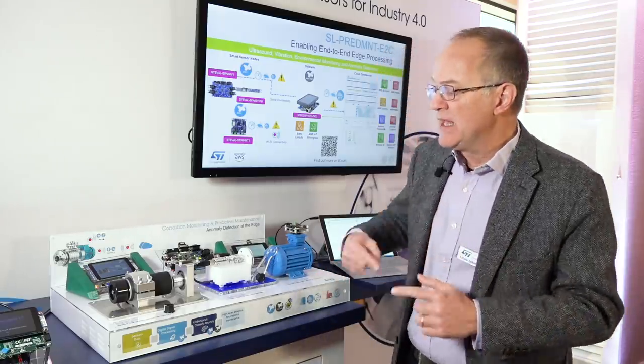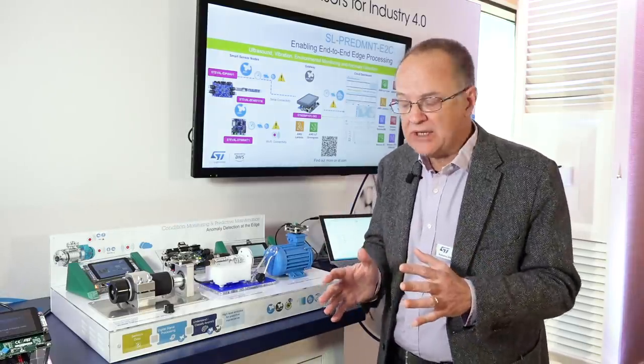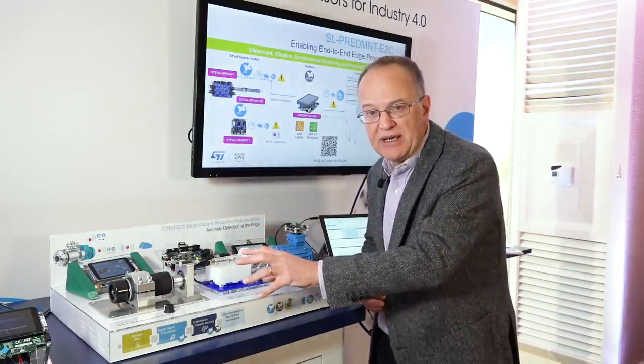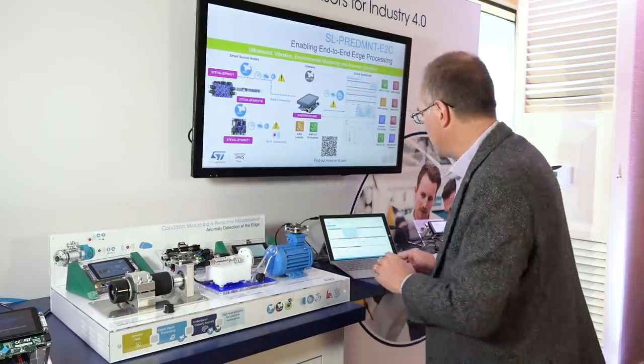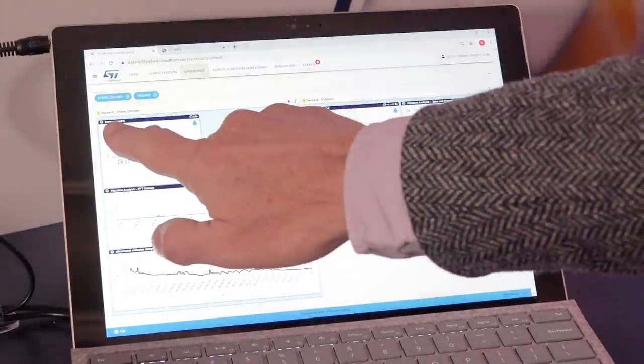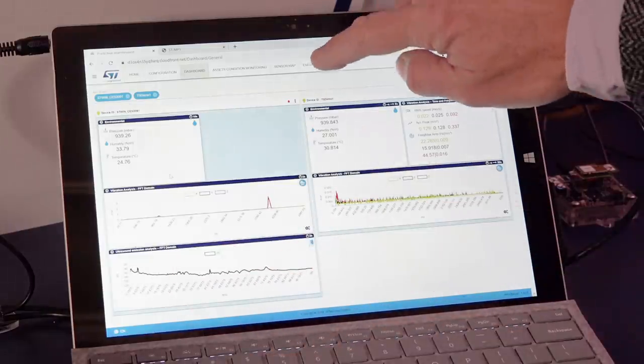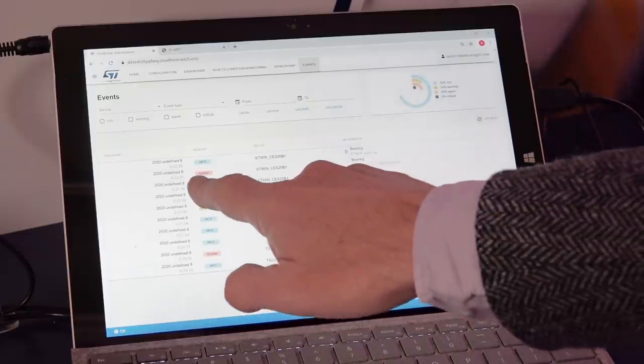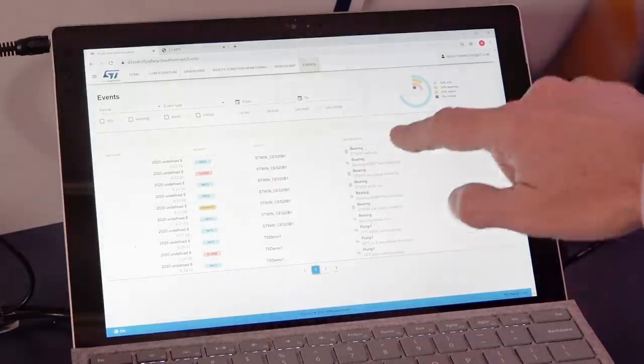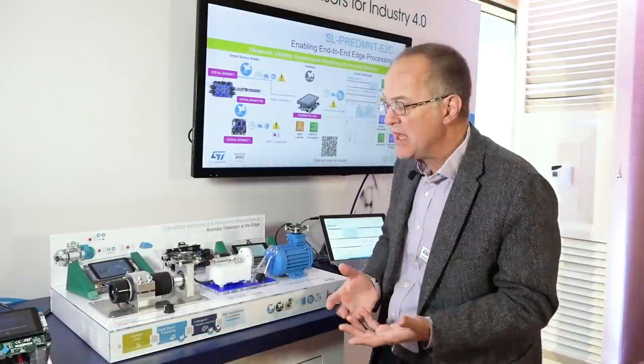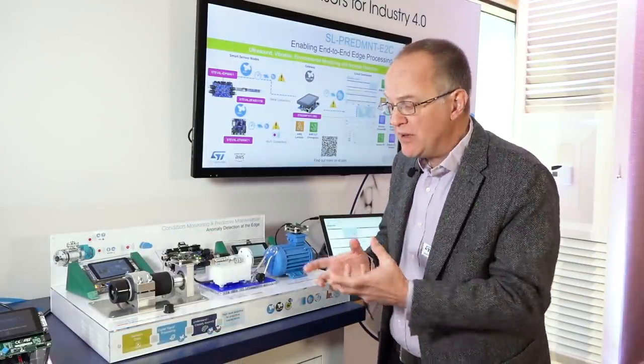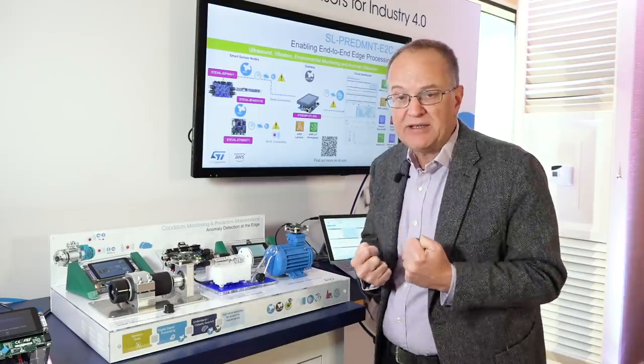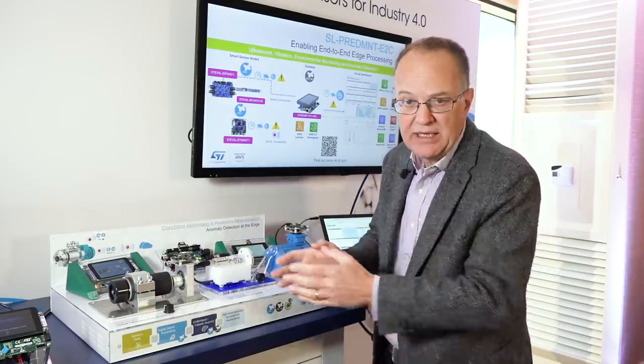In low power mode the system checks the vibrational, inertial, and acoustic data of these systems and runs continuously. Now let's inject a problem into this bearing by simulation. We have injected the problem and the system has just woken up from low power mode. A warning has been raised, as you can see in the cloud interface, notifying that something strange is happening and beginning to send actual data to the cloud so it can be further analyzed. If we inject an even stronger problem into this bearing, simulating worse damage, the system can also autonomously raise a more important alarm, calling for help immediately.